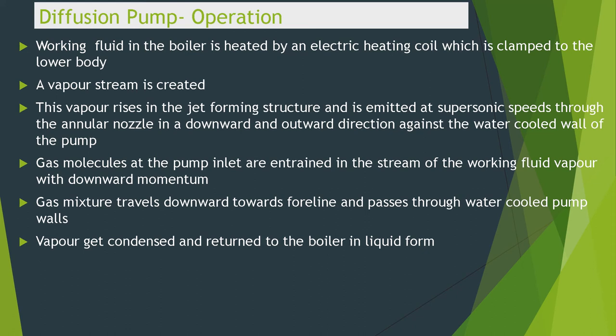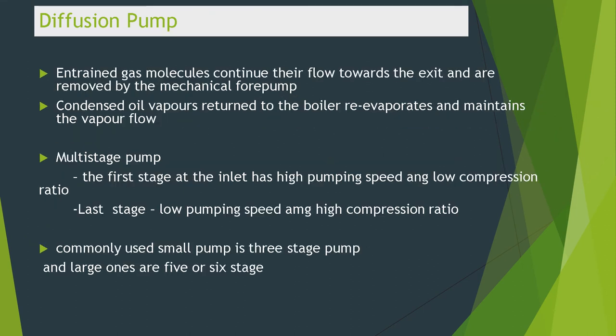The gas molecules at the pump inlet are entrained in the stream of working fluid vapor with downward momentum. The gas mixture travels downward towards the fore line and passes through the water-cooled pump walls, where the vapor gets condensed and returns to the boiler in liquid form. The entrained gas molecules continue their flow towards the exit and are removed by the mechanical pump. The condensed oil vapors return to the boiler, re-evaporate, and maintain the vapor flow.